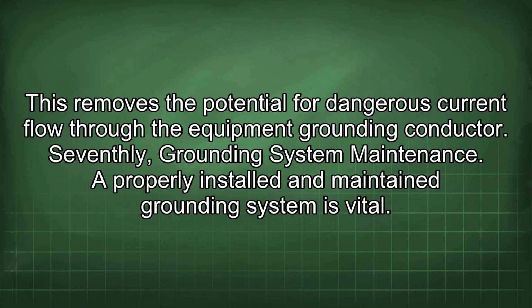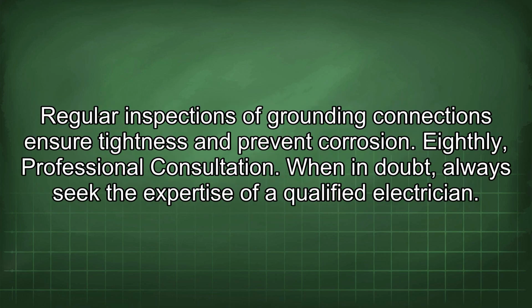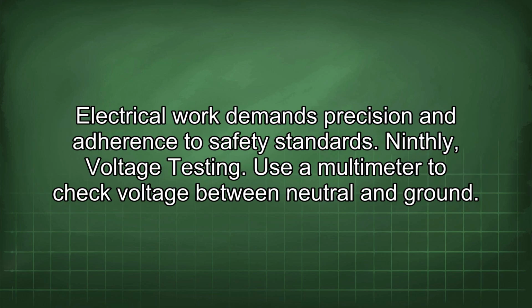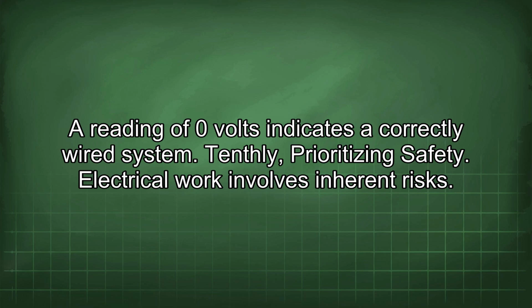Seventhly, grounding system maintenance. A properly installed and maintained grounding system is vital. Regular inspections of grounding connections ensure tightness and prevent corrosion. Eighthly, professional consultation. When in doubt, always seek the expertise of a qualified electrician. Electrical work demands precision and adherence to safety standards. Ninthly, voltage testing. Use a multimeter to check voltage between neutral and ground. A reading of 0 volts indicates a correctly wired system.